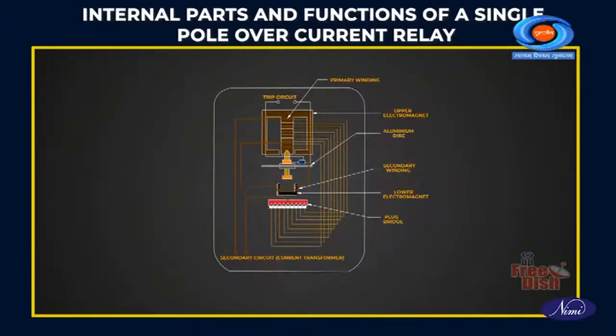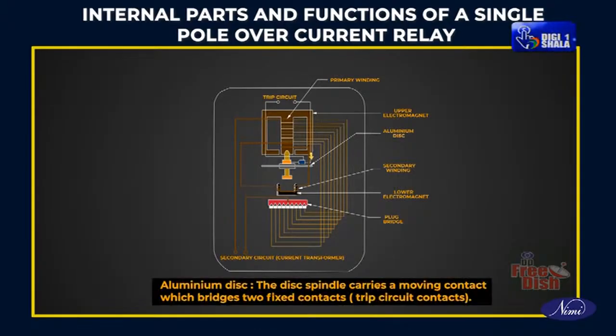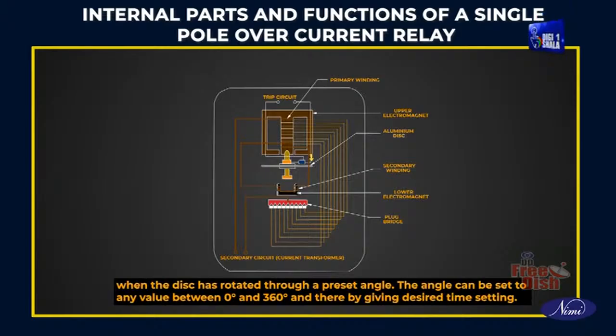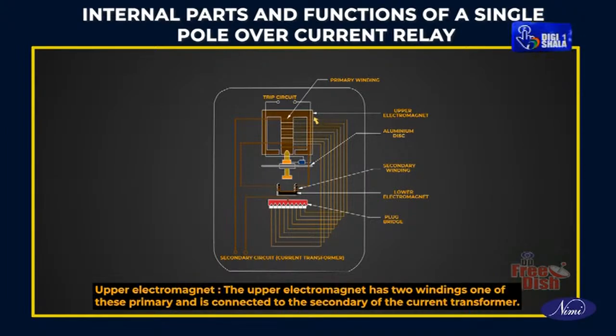Internal parts and functions of a single pole overcurrent relay. Aluminium disc: the disc spindle carries a moving contact which bridges 2 fixed contacts when the disc has rotated through a preset angle. The angle can be set to any value between 0 degrees and 360 degrees, thereby giving the desired time setting. Upper electromagnet.